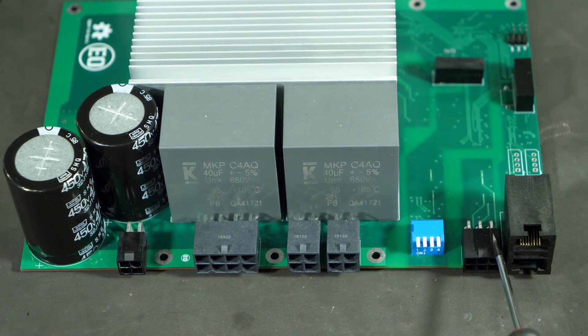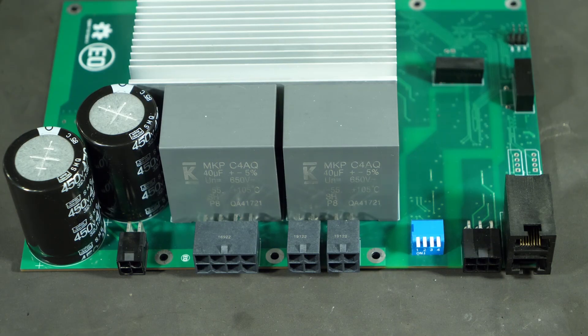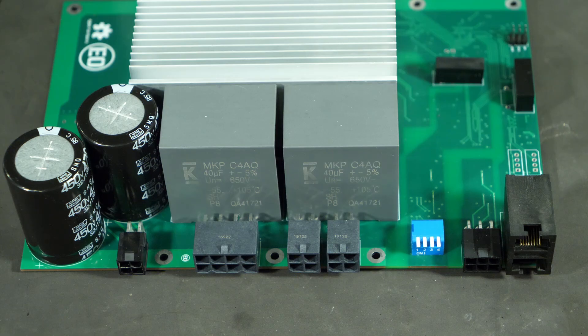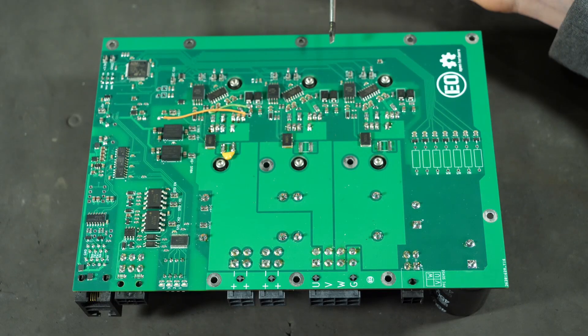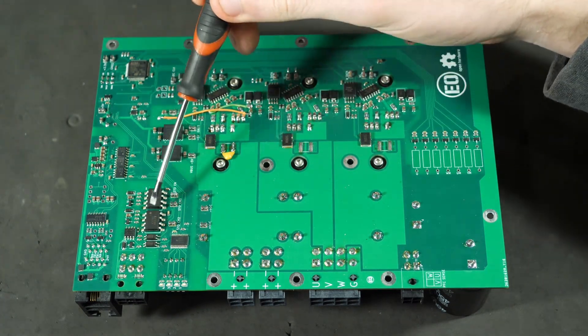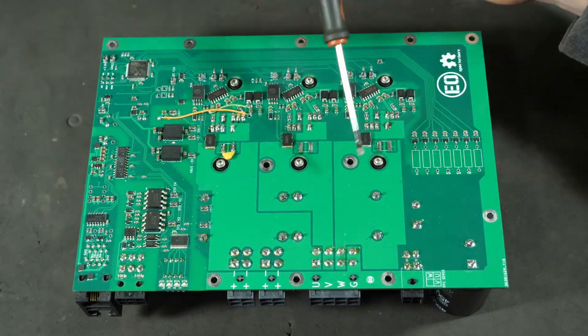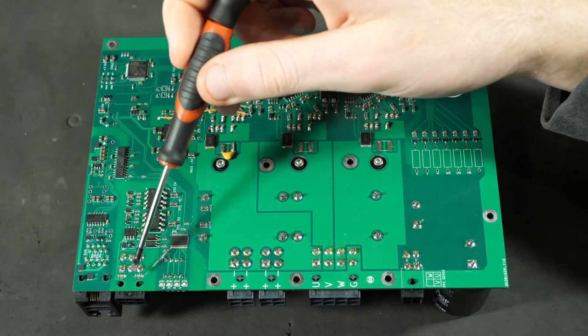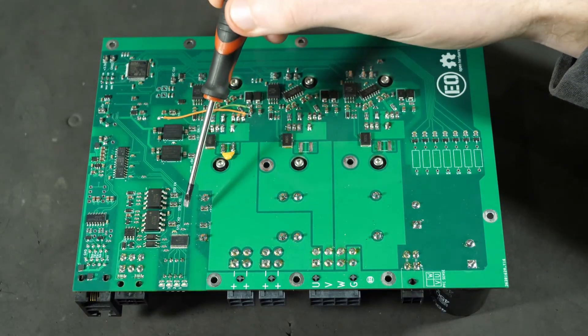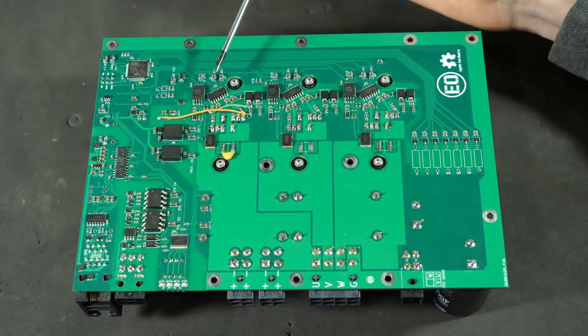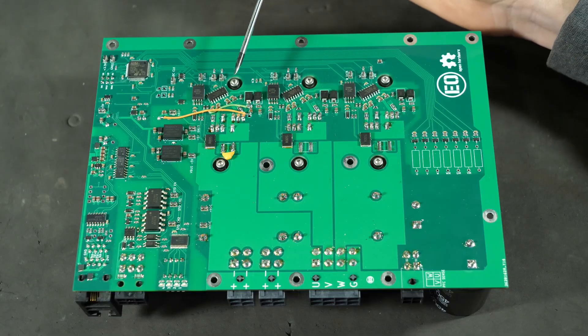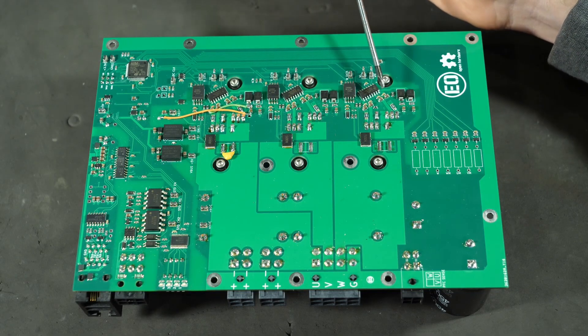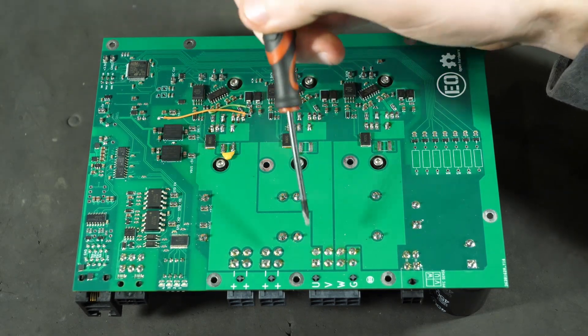The next connector is for something called Safe Torque Off, or STO. When working with high power motors, it's important to make sure there are safety systems in place. Most of the time this is just an e-stop button that somehow disconnects the main power supply. Safe Torque Off provides another way of ensuring the drive cannot output any power. It has two inputs that then go through opto-isolators, one of which goes to the gate drivers and disables them. That way, the gate drivers cannot turn on the output FETs to output any power.